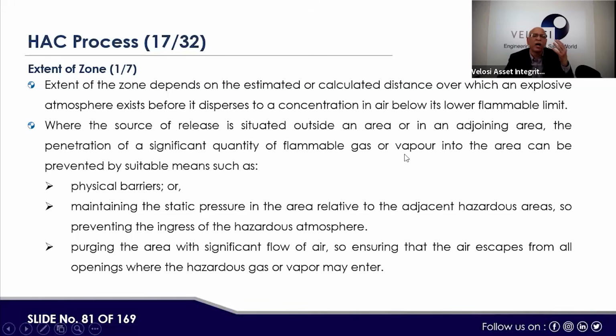Other areas, like if a hydrocarbon may come from neighboring areas, like a control room we need to control. Otherwise, we have a source of release and how far it can extend. There are two parts. One, where hydrocarbon or flammable liquid may release from the point source. The other is a neighboring facility from where hydrocarbons are released, and the same hydrocarbon with air or wind can penetrate to our area. In that area, we need proper barriers and positive pressure inside, so that ingress of hydrocarbon into that particular equipment or apparatus can be avoided.